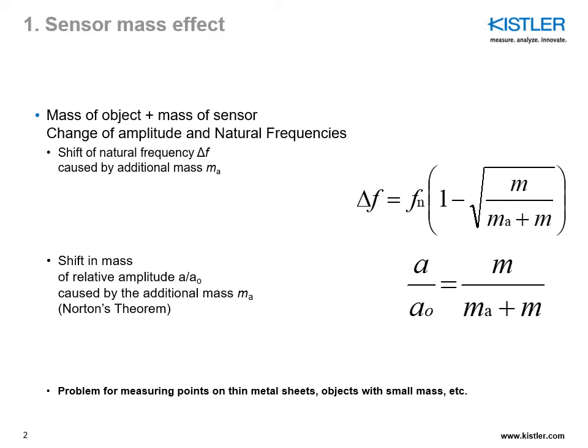The first topic we're going to address is the sensor mass effect. You want to understand how much your sensor is going to influence the behavior of the structure under study. The dynamic properties of a structure are dependent on its mass, rigidity, and damping, as well as the way the sensor used for measurement is being attached to it. If the mounting of an accelerometer applies some additional mass to the structure, these dynamic properties can change.